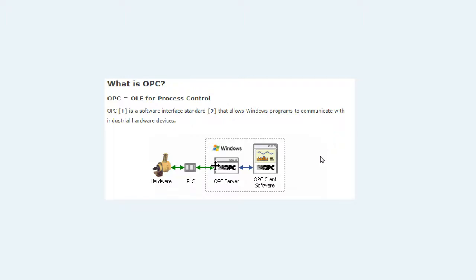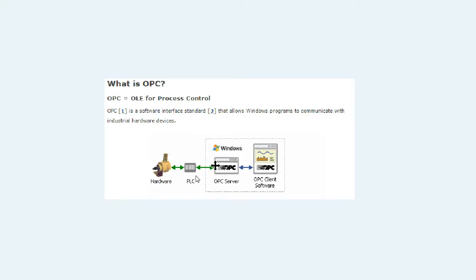The subject of this presentation is OLE for Process Control, or OPC. This is what StripChart OPC relies on to communicate with a PLC. OPC stands for OLE for Process Control, and its purpose is to provide a bridge between a Windows PC and a PLC that's controlling some machine. The key concept is that the OPC server resides on some PC, and that's what's communicating to the PLC.